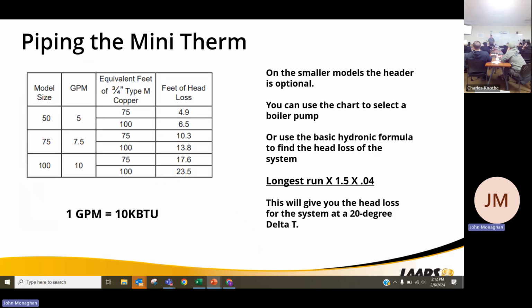So we're talking about piping and what we can move through them. This is right out of the I&O manual. The model size 50 needs 5 gallons a minute. Equivalent, either 75 feet of copper or 100 feet of copper is going to be your friction head loss. And it's going to basically tell you what size pump that you need there.